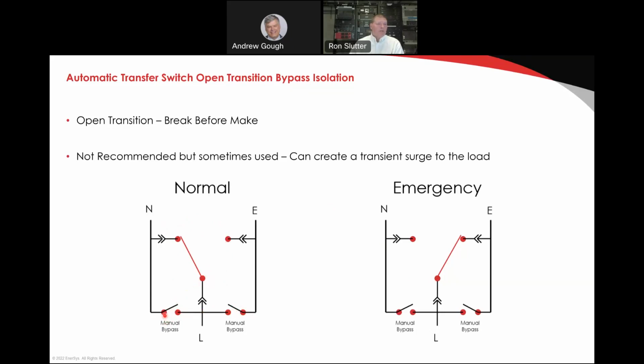And so if we lost, say, the manual bypass for the normal side is closed because we lost the ATS, and we lose utility, then manually the person would need to open the manual bypass and then start the generator and see that the generator is producing good power and then close the manual bypass on the emergency side. Okay. So what does this do? This gives us the ability to deal with significant issues within the ATS without getting a rental or without getting additional equipment. We can use this equipment to still maintain service to the facility while we deal with the problems that may be associated with the automatic portion of the ATS.